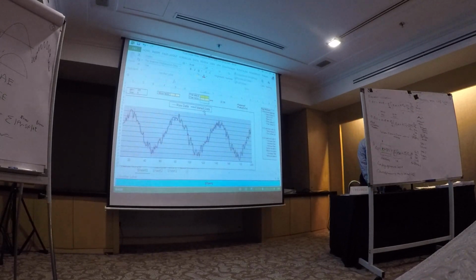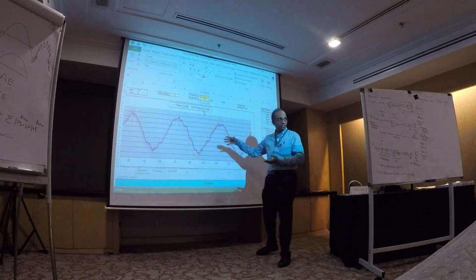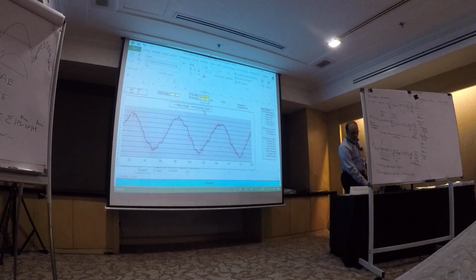So I put a 1 second filter. The blue line is the 1 second filter. It's here. Now watch what happens when I increase the filter time. So it gets better, right? I put 3 seconds of filter. And the blue curve starts to look nicer, right? And let's put in a bit more filter time and you see what happens.